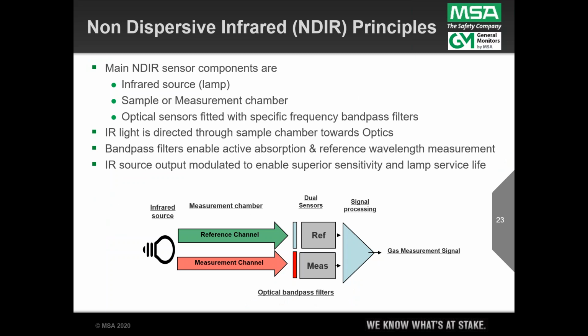That set the stage for another technology that doesn't have that same weakness, and that's the NDIR, or non-dispersive infrared. This is a non-destructive measurement. It's an optical measurement of gas. What are the components? I've got those shown across the bottom. An infrared lamp on the left. You've got a measurement chamber in the middle where the lamp energy shines through, and then you have the electronic section on the right, and that includes the sensors. We have an active sensor called the measurement sensor.